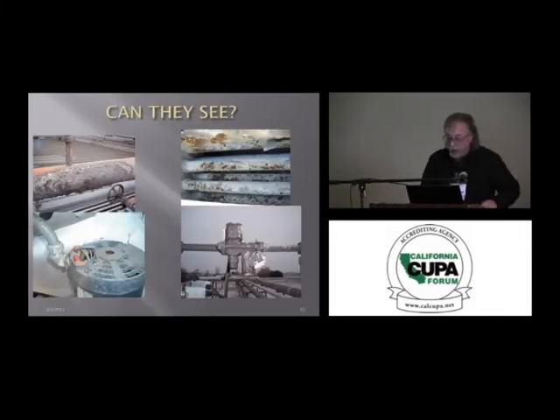Okay. Another problem we're having out there, or challenge I should say, is with new evaporative condensers, or some people call them cooling towers. That's your piece of machinery outside that has the water and the air going through it to remove the heat. We're having a terrible problem with white rust. And not only at startup, but the white rust is coming back again years later. The sites should be looking at their condensers almost every month. Well, actually, they should every month. We have to passivate the equipment when we put it in, or we used to be able to use chromates in the water. We can't use that anymore because it's a heavy metal.